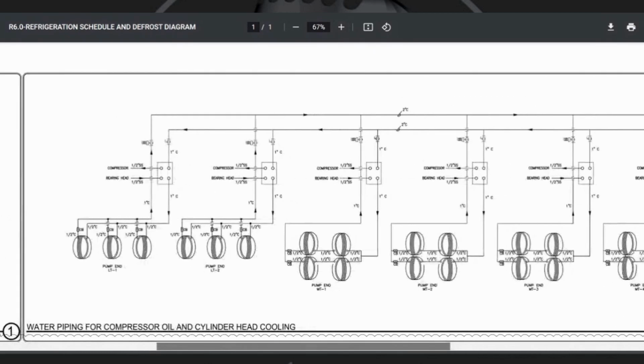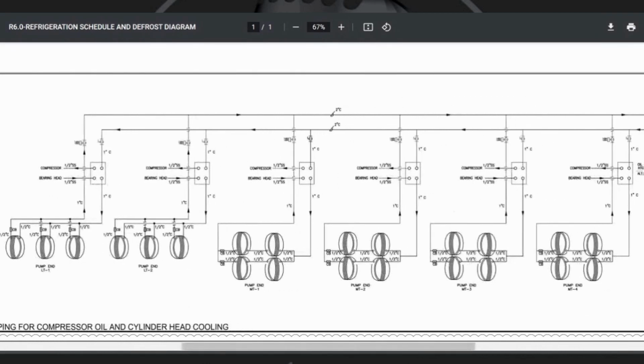This drawing shows water cooling on the low stage compressors, and we did install it this way, but we found out that it created more problems than it helped. As a matter of fact, at one point we actually froze the water in one head and cracked the cover plate. Didn't hurt the compressor or the valve plate, but cracked the cover plate. So we've abandoned the need for water on the low stage compressors.